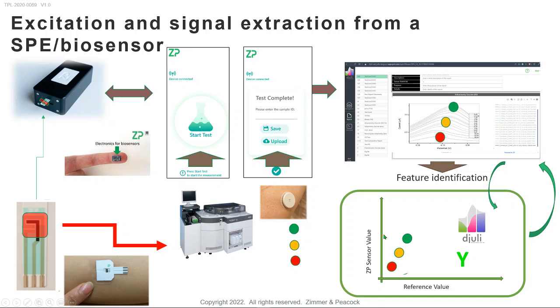That alignment process can be fast or very hard, depending on the sample, reference device, and application — whether it's a discrete or continuous measurement. What we're saying is: even if you come to ZP just for the screen printed electrode, if you put all the emphasis on controlling the screen printed electrode and don't consider excitation and signal extraction, you'll end up having to make a device with very small tolerances and therefore a very expensive device with low yield.